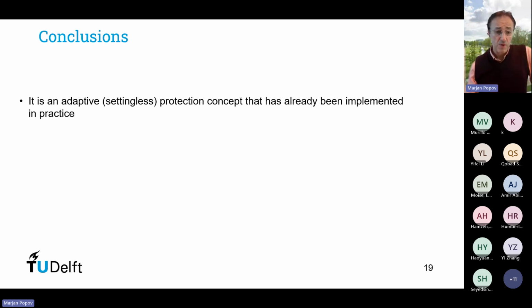Finally, this has been compared with the existing solution, and we know that the existing solution normally uses the impedance-based trajectory concept, which is very different from this one. The advantage is that we found this is faster, but also is settingless. So we don't have to provide any kind of settings except those in which the algorithm operates.